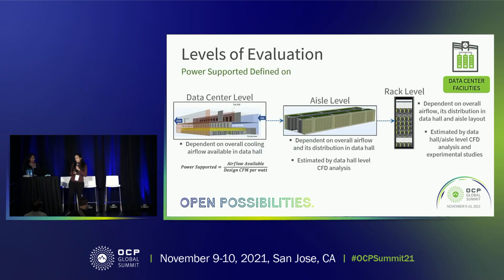When we talk about the IT power that we are able to support, or the cooling capacity that we are able to support, we are looking at different levels of evaluation, starting with the data center level. For the data center level, really this is a very high bird's-eye view of how much power we can support. At the data center level, the power supported really is dependent on the overall cooling airflow that is available in the data hall.